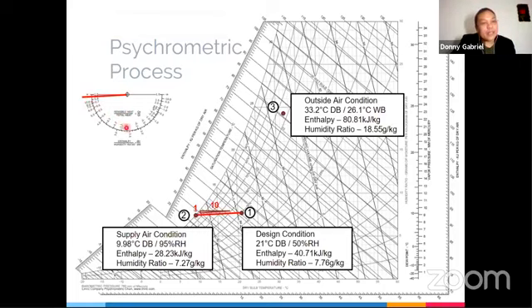Using this as our guide, 90%: 0, 10, 20, 30, 40, 50, 60, 70, 80, 90. So this line is 90%, or sensible heat to total heat is 90. This line now is parallel to this line. Remember, we are using the psychrometric chart. We are dealing with the graphical representation of the properties of air. So having 10% latent and 90% sensible heat ratio, we were able to draw this line. The angle of this line is the same as the angle of this line. So this line and this line are parallel.